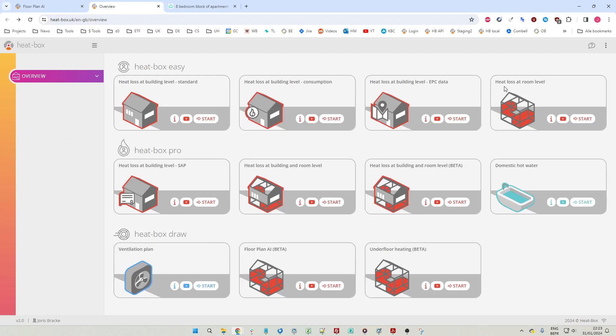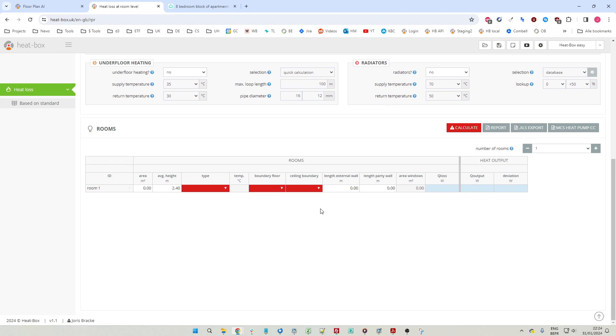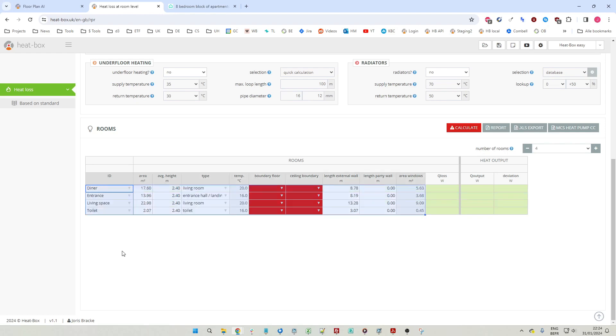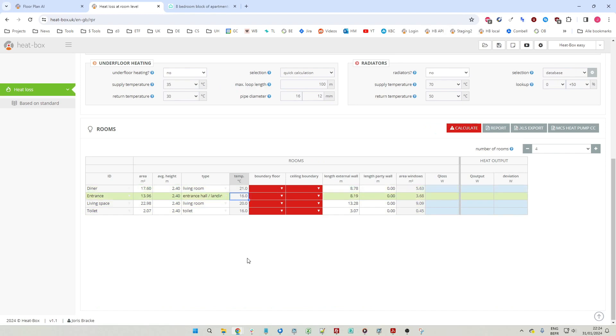We go to the heat load calculation at room level and click the start button. To make a heat load calculation at room level we have to answer some questions - how to answer these is discussed in another video. Here we're more concerned about the table. To add the dimensions of the rooms, we say we want to add four rooms, click on the first cell, and hit Ctrl+V to paste the data from the floorplan AI tool: room name, surface area, room height, and type of room. The type of room also determines the room temperature, but we can change this manually - for example, the living room or diner can be set to 21 degrees.